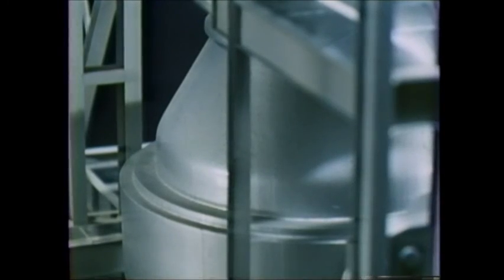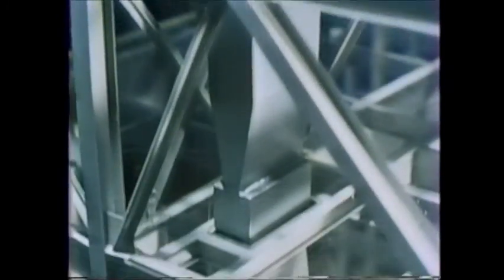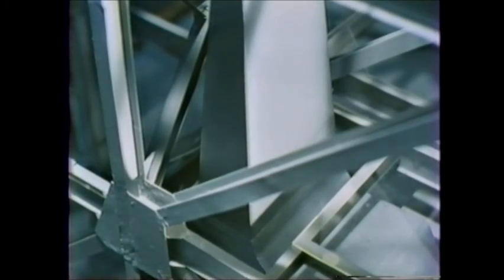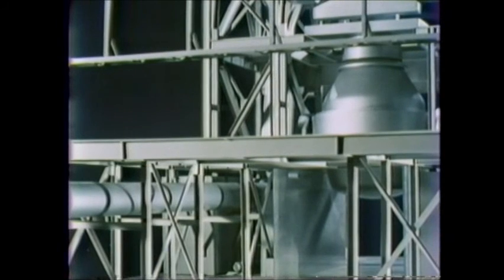Here are the highlights of the OG process. Carbon monoxide generated in the vessel is sucked out through the hood in such a way as to prevent leakage from the vessel mouth. Then the gas is saturated in the quencher where coarse dust particles are collected. The remaining finer dust is removed in the venturi. The cleaned gas is either discharged into the atmosphere through the flare stack or recovered into the gas holder through the three-way valve by means of the induced draft fan.